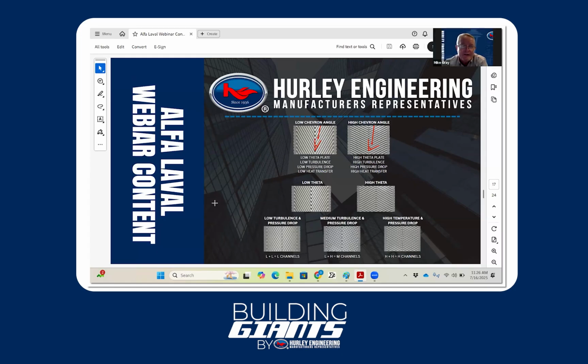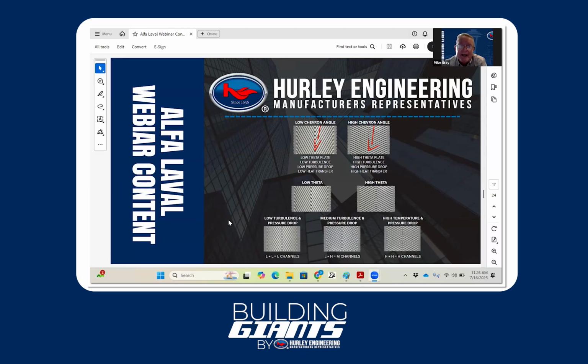As Dave mentioned in the list before, you've got different plate patterns available, and you want to make sure your manufacturer has options for you. Most of them will have some type of chevron pattern, whether it's a low angle or a high angle chevron pattern. When you put those patterns together, plates one on top of each other, you get what they call a low theta or a high theta configuration. Combining those together, you get low turbulence, medium turbulence, or high turbulence, which is pretty important when transferring heat from one side to another.